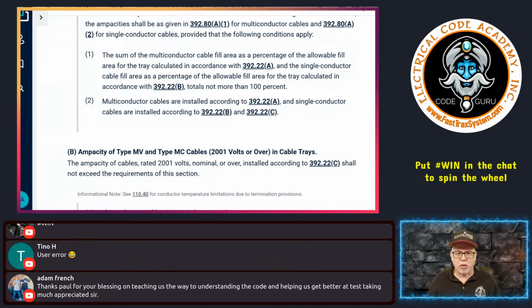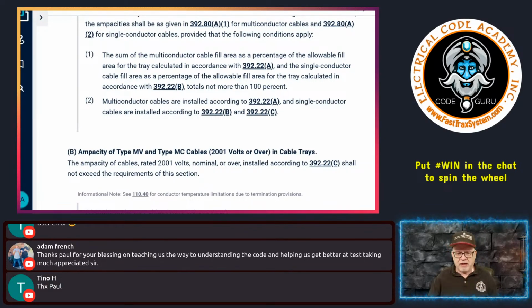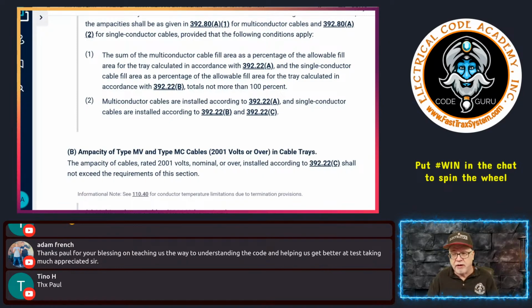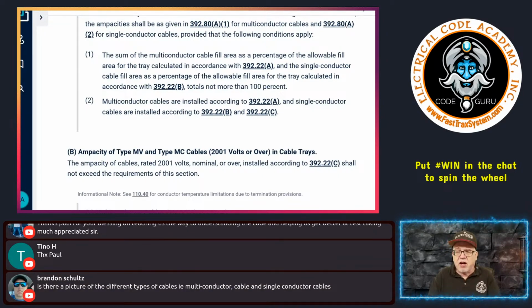Those are pretty straightforward. Very rarely do we mix the two. I mean, you could mix the two, but usually all we're saying is treat each one of them separately when you're doing the ampacity values. Treat them separately, okay? And then we're just making sure that the combined fill value for those conductors and cables that are in there is not going to exceed 100% of the cable fill percentages of that cable tray. Makes sense? I don't have any pictures.